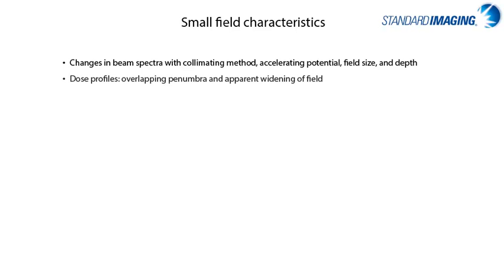Extending on this definition, small fields have a varying spectra depending on the collimation methods, accelerating potential, field size, and depth. Further, the dose profiles exhibit overlapping penumbra when the fields get small, which results in an apparent widening of the field which we addressed previously. And finally, there is a drop in output from the expected ideal as the field size decreases as well.